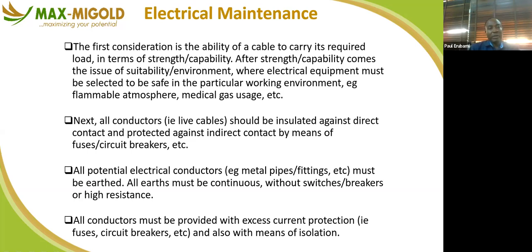Like I told you earlier on, the first one is the ability of a cable to carry the required load. So we have that, or we have treated this. So don't underrate your cable. Instead, go for a higher rating because of future expansion and other things that may be required for the future. So all conductors and live cable should be insulated against direct contact and protected against indirect contact by means of fuses and circuit breaker. We talked about the importance of circuit breaker and fuse in our early slide. So you have to ensure that all these live cables are protected. Don't compromise on that. Ensure they are protected.